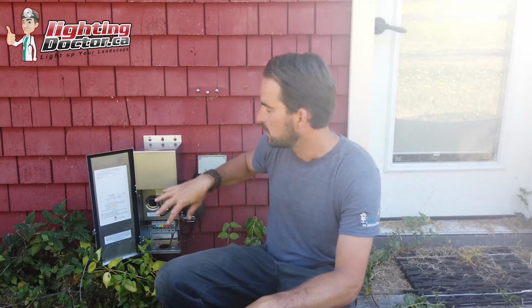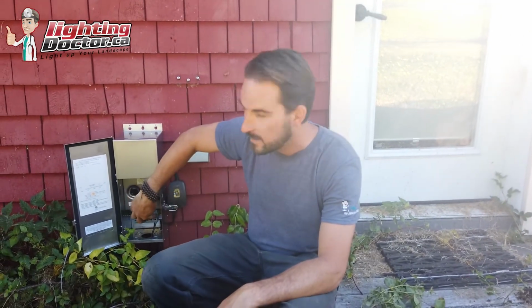With LED systems now, that's not really the case, because if you're buying any good quality LED lighting fixture, they're going to generally operate between 10 and 15 volts, which means there's a large gap of voltage drop that you can allow for. The general rule of thumb we always talk about is if you have a transformer like this that has a 15 volt tap, you always want to put your longest run on there so it allows for the most voltage drop.